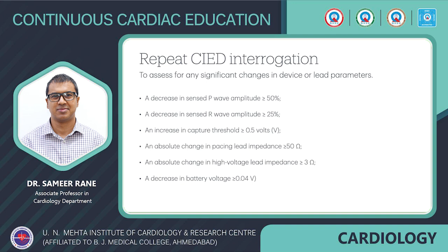They were a decrease in sensed P wave amplitude of 50% or more, a decrease in sensed R wave amplitude of 25% or more, an increase in capture thresholds of 0.5 volts or more, an absolute change in pacing lead impedance of 50 ohms or more, an absolute change in high voltage lead impedance of 3 ohms or more, and a decrease in battery voltage of 0.04 volts or more. The patient then returns to their routine CIED interrogation and surveillance plan.